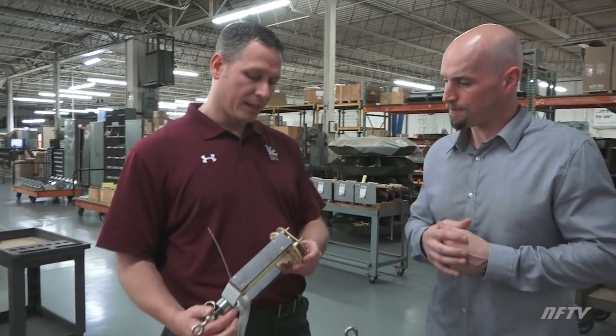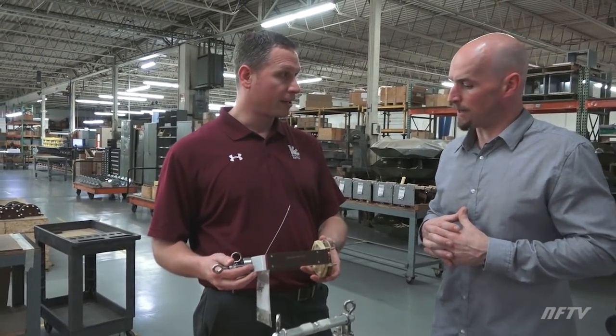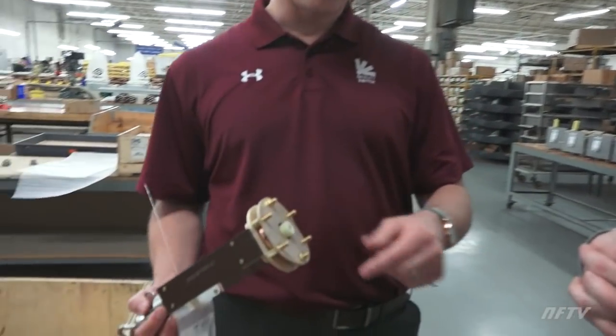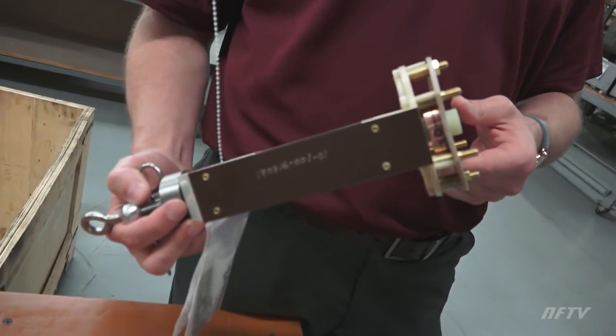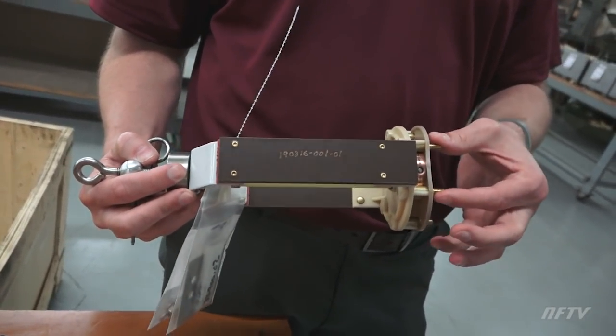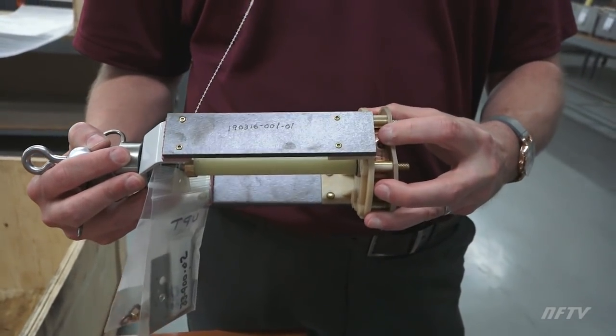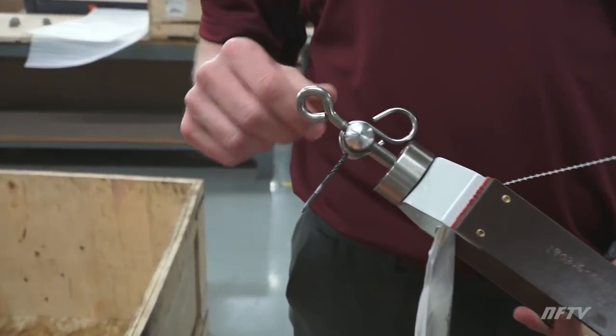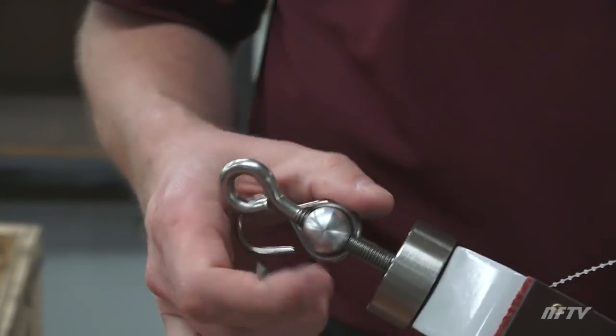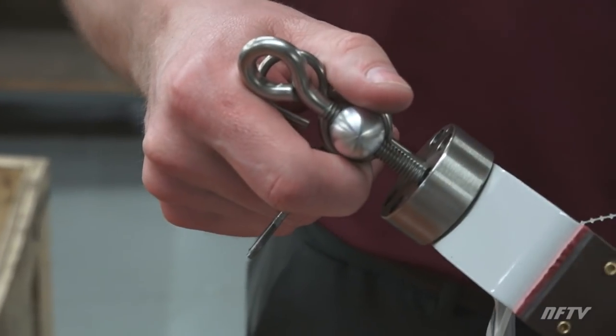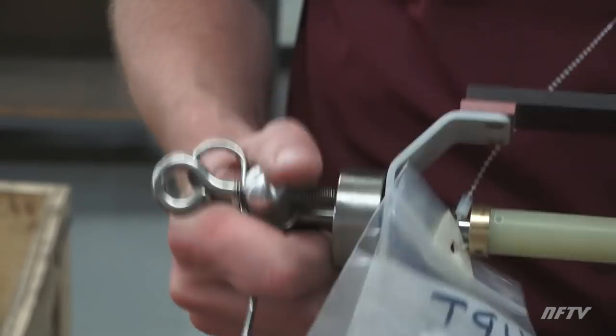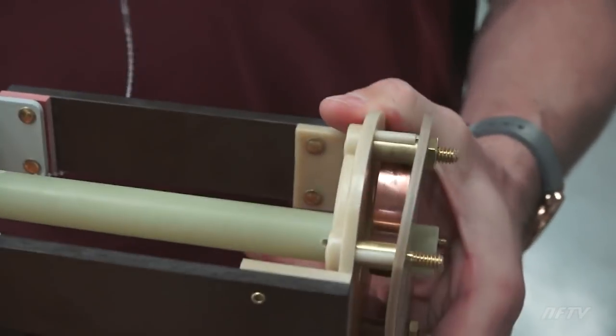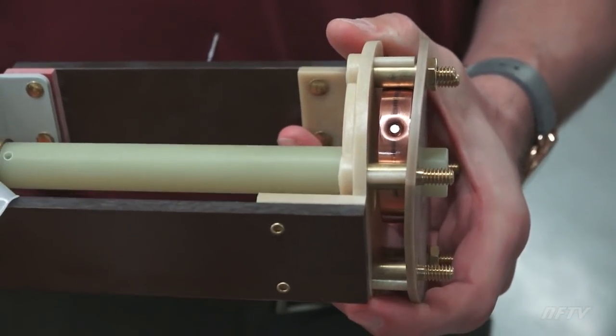So Jeremy, can you show us exactly how this particular device works? Sure. Basically, there is some assembly required by our customer. They'll install this inside of their transformer and run tap leads that pick different voltages off the transformer winding. Our switch bridges those two tap leads. We have a moving copper contact and a handle assembly operated by the utility line worker on a stick outside the transformer, which rotates our moving contact so it snaps between these two positions, allowing them to adjust the voltage output of that transformer.